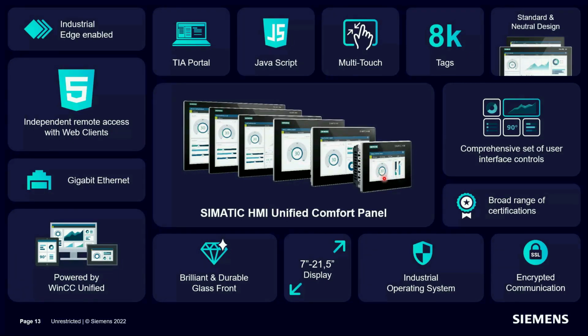So all the controls have a very similar look and feel - the sliders, the gauges, the push buttons, the alarm controls. Whether you're configuring WinCC Unified to run on the web interface on an S7-1500 controller, a WinCC Unified Comfort Panel, or a full SCADA system, from an operator and engineering perspective the engineering tool is exactly the same, and that's very important for commonality and ease of use.